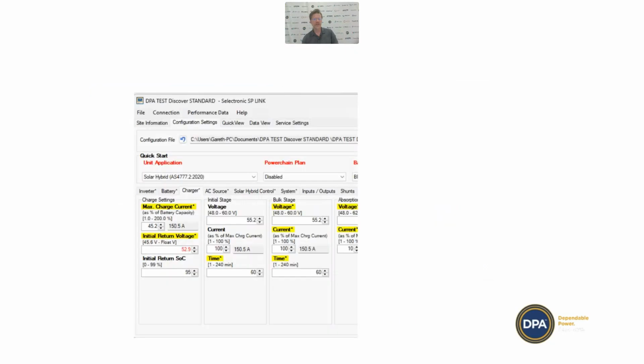You're then going to finish the wizard, and you'll be through into the configuration settings. There are just two values you need to adjust: the max charge current value, and the size of the system. So you're going to put in the number of rack mount batteries, but then you'll need to go in and change the amp hour size of the system to match the number of Helios batteries you actually have, so that it knows the size of the system.